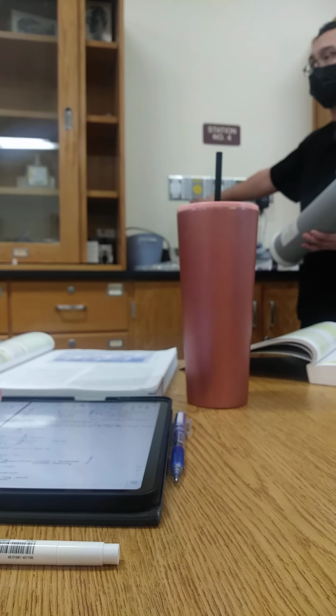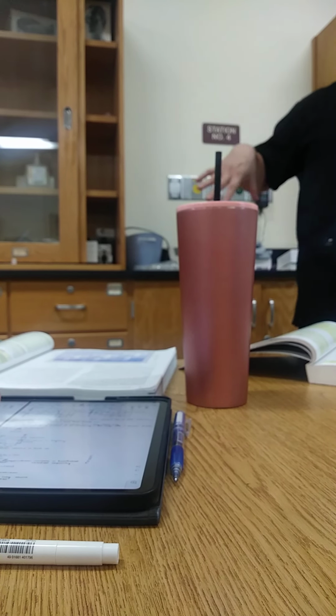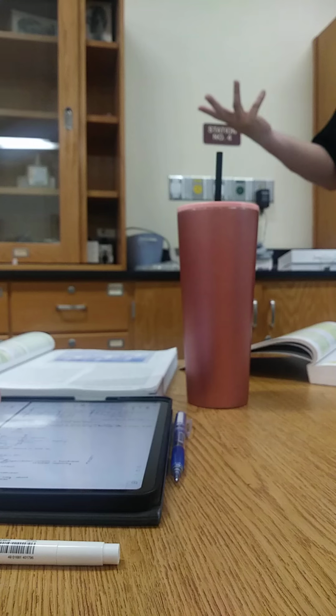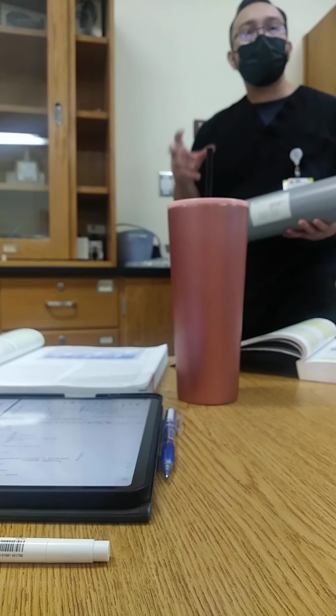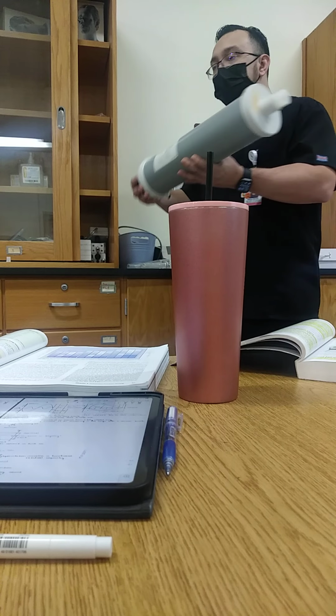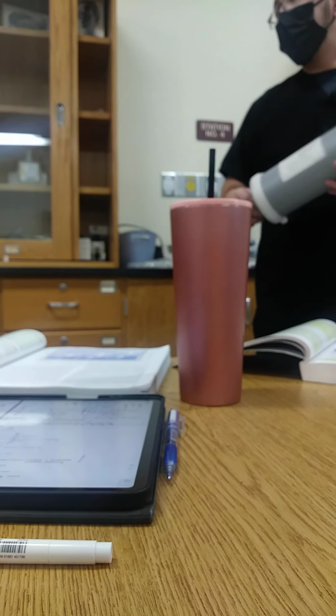Okay. So it is used for calibrating your devices. Because the whole point of these devices is that we're supposed to measure a volume and a flow. And how do we know if it's even accurate? So you have to have a way to make sure that the device is calibrated correctly and working. So this is the device that we are going to use and you guys can practice with, okay?